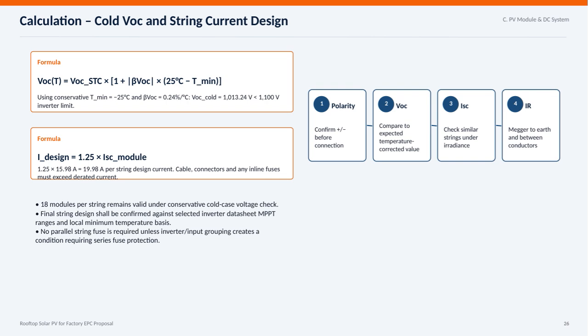It's important to note that parallel string fuses are typically not required unless the inverter or input grouping configuration creates a need for series fuse protection. Finally, 4 key checks are highlighted: verifying polarity before connection, comparing VOC to expected temperature-corrected values, checking the short-circuit current of similar strings under irradiance conditions, and using a megger to test insulation resistance to earth and between conductors. These steps help maintain system reliability and safety.